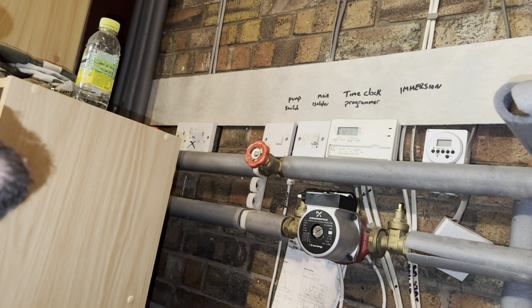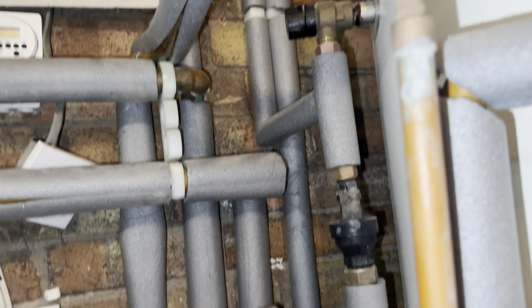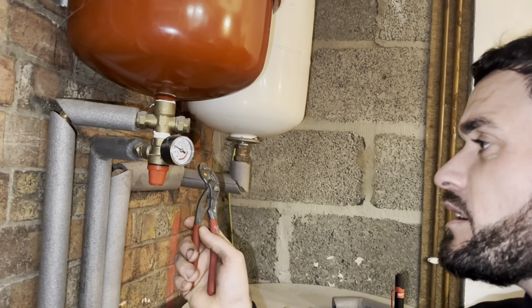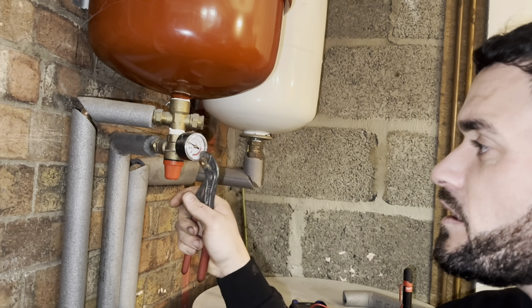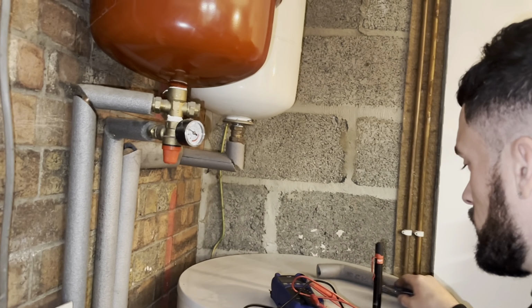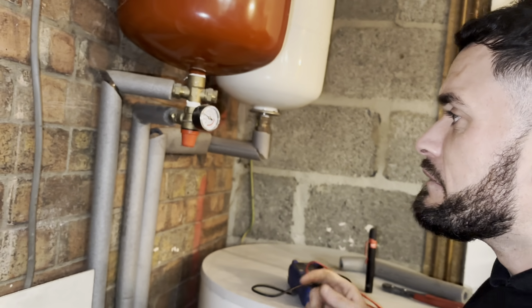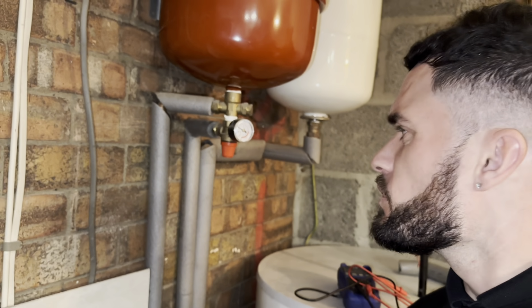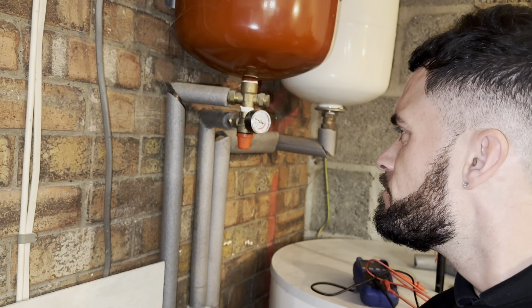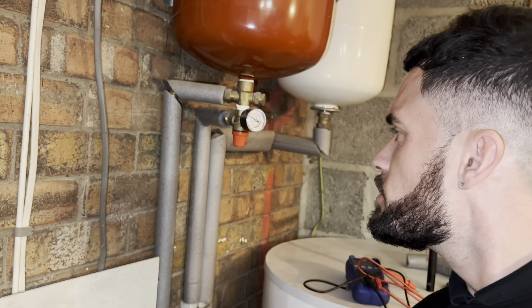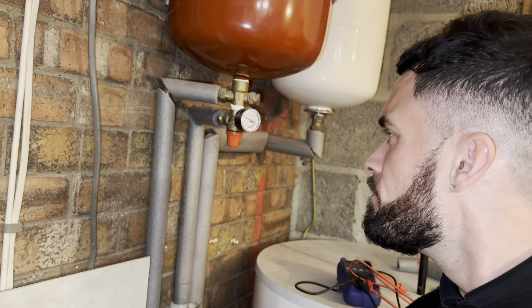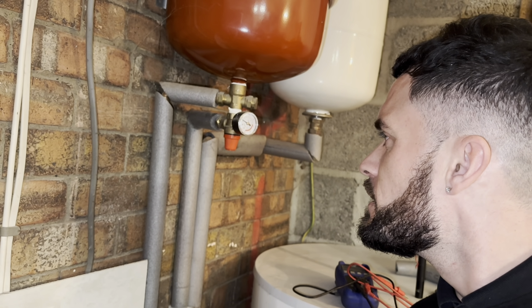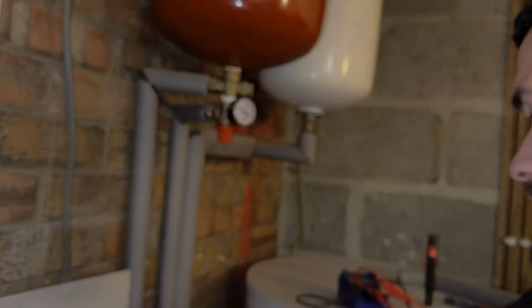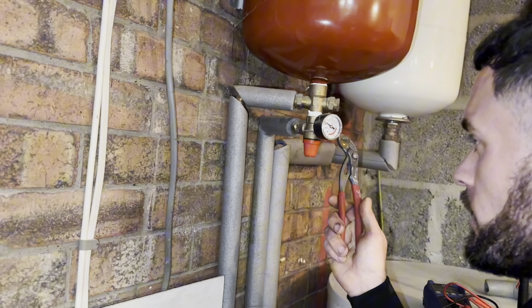Yeah, the amount of water that's not been in the system - by that filling, I'll keep an eye on that gauge. Them boilers, like I say, I've not got a pressure sensor. I don't want to go up as well on my gauge though. Could be shot, that - just a fault. Gauge could be as well, yeah. I don't want to put too much in and over-pressurise it, do you know what I mean? But then I've got to see if I get...